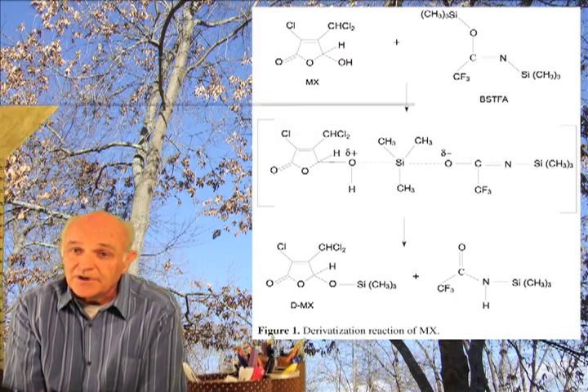Let's put together a very quick example. We're going to run two samples. We need a blank, a standard—remember this is a two-point calibration but one of them is zero, so we only need one standard. Blank, standard, we need a control which is an independent standard essentially, and then we have two samples. So we have five tubes.